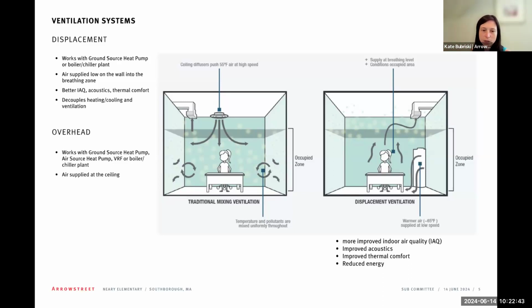Potentially, we won't talk about this today, but potentially CO2 demand control ventilation. And so the air quality will be good, but it is better in the displacement system just because of the fact that it's not mixing in the space. It's really supplying low and returning high. There are some improved acoustics and thermal comfort because you're supplying that air down low. You don't have to supply it at as high a velocity because you're not trying to mix the system. It's really relying on the buoyancy of the temperature in the space.